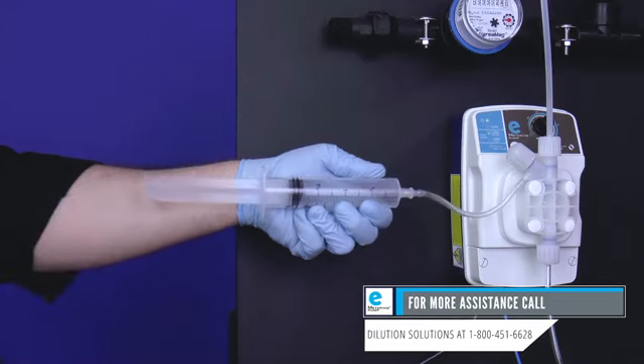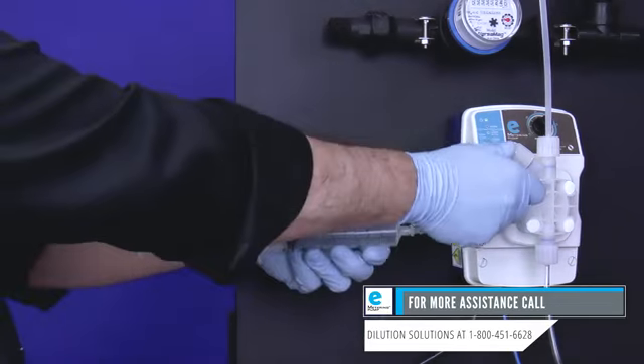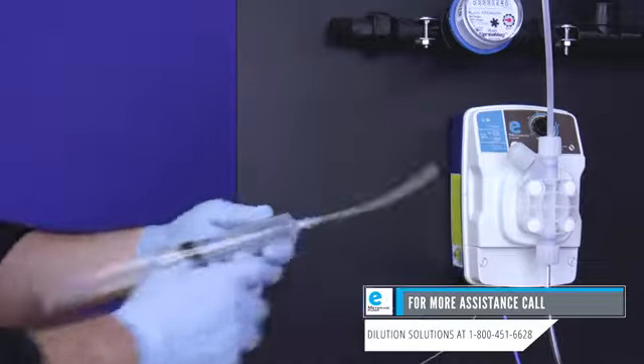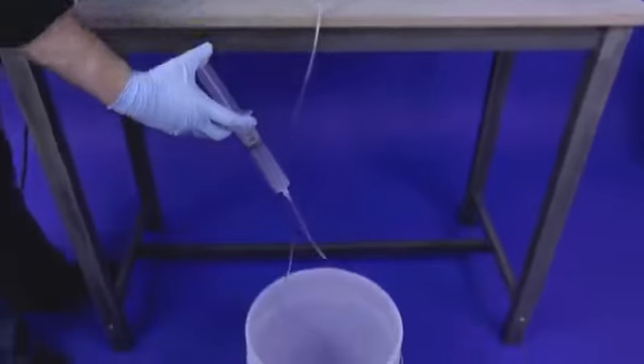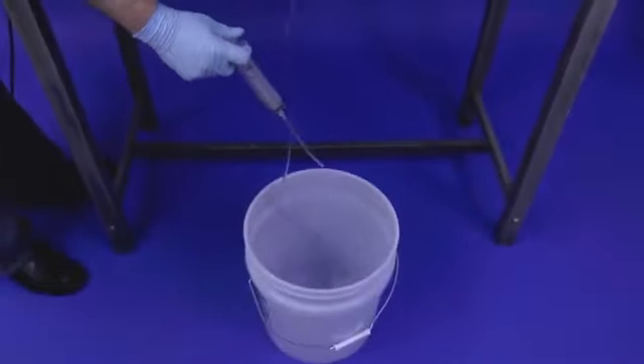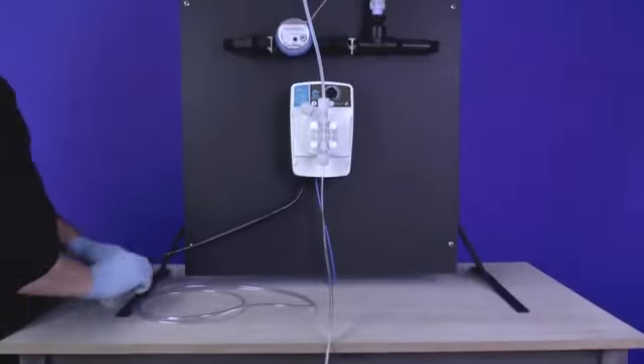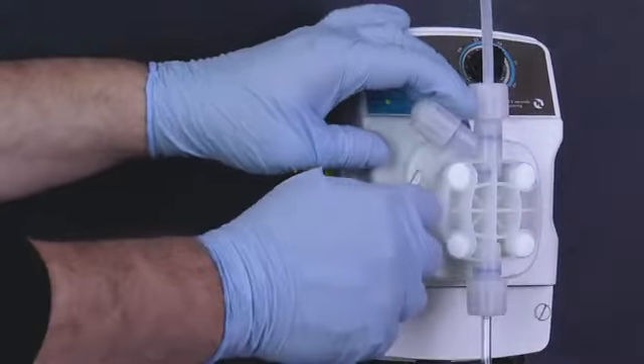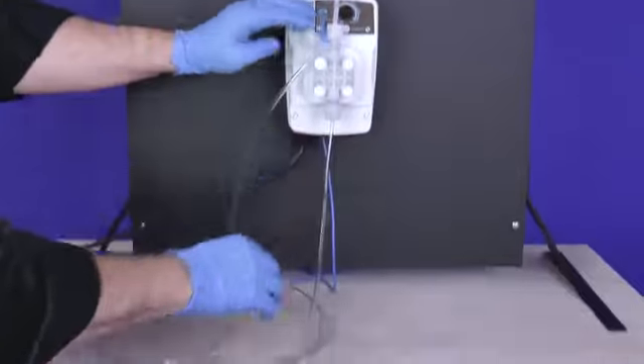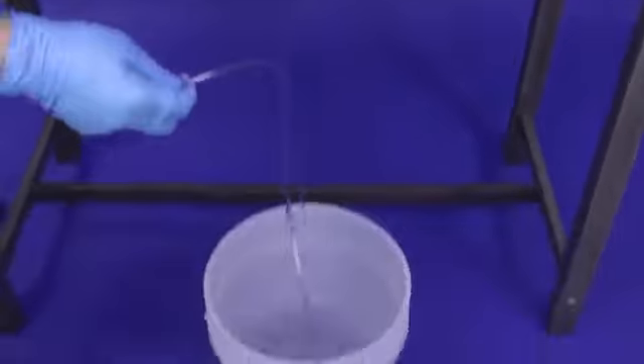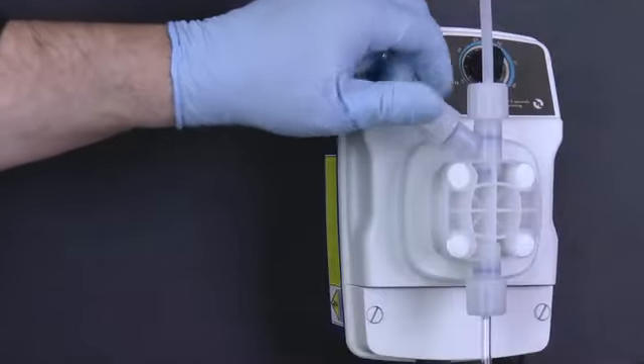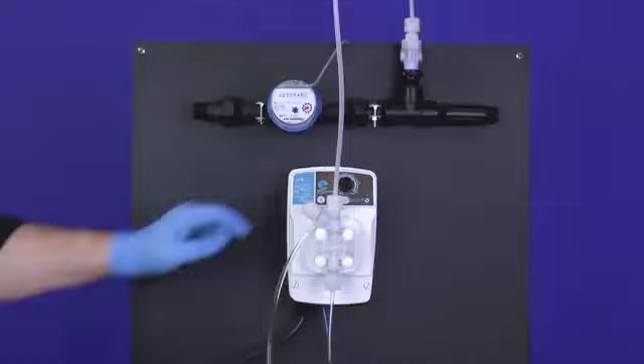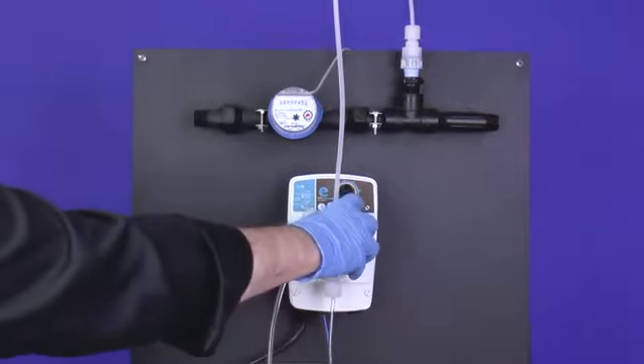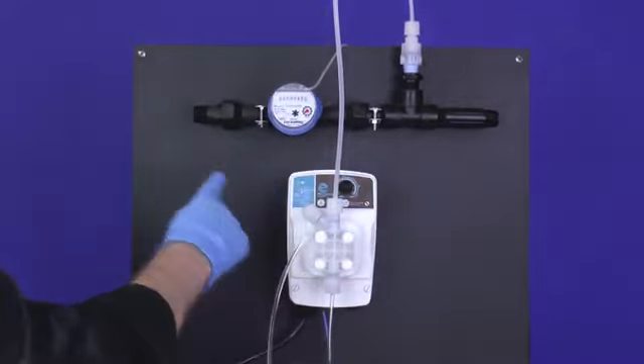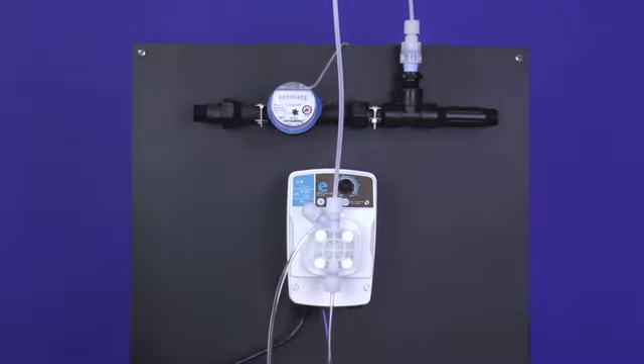This may take a couple of tries. If no chemistry enters, call Dilution Solutions for assistance. Eject the chemistry from the syringe into the chemical bucket. Slide the bleed-off tubing back onto the air bleed barb and place the tubing back into the chemical bucket. Now close the air bleed valve by turning it clockwise. Start the eMP and run a few gallons of water through. The eMP should now be drawing chemistry and functioning properly.